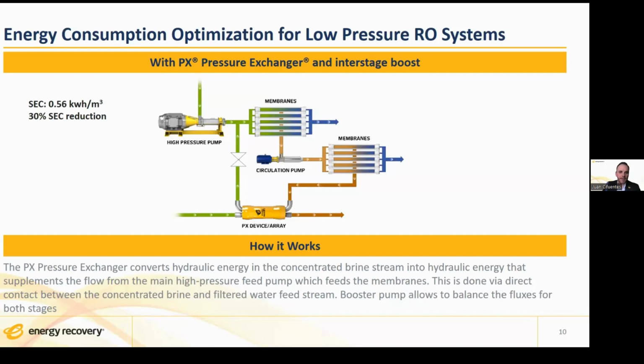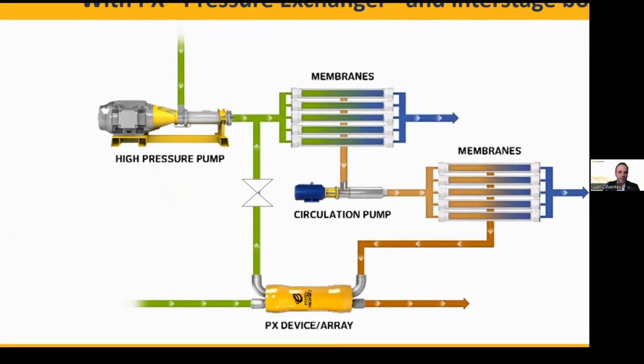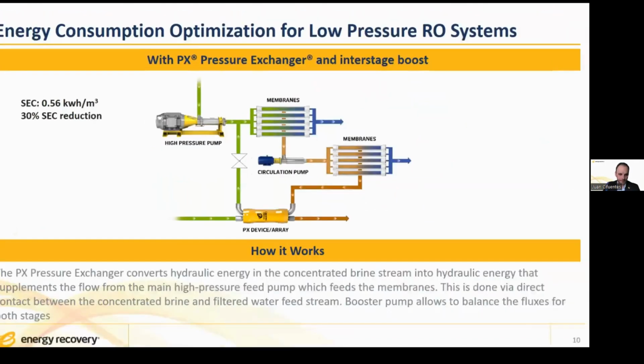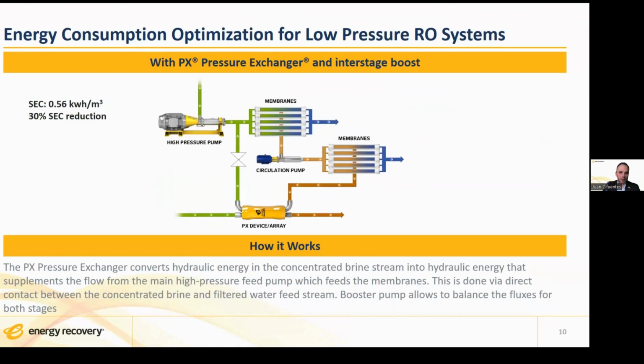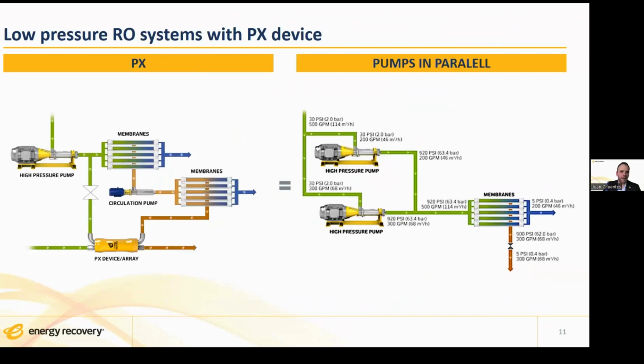How does it work? The PX takes the hydraulic energy from the brine and transfers it to the feed directly, by direct contact with some part of the feed. And it is combined with the high pressure feed developed by the high pressure pump. The booster pump, or the interstage booster pump, allows us to balance the stages and also overcome the head losses in the two stages. It means that the PX plus the circulation pump works as a parallel pump to the main high pressure pump, reducing the required flow of the high pressure pump to just the permeate flow.